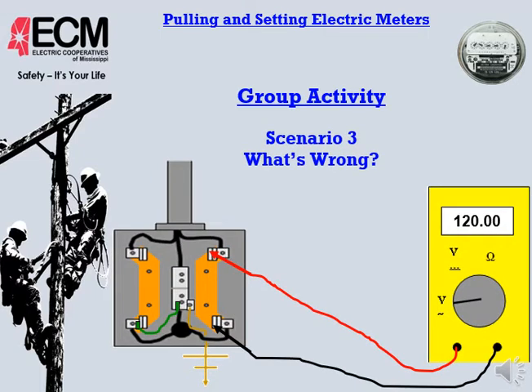Okay, in scenario 3, we get to this point and we're checking voltage and we get 120 volts. Again, we should not get any voltage here. It should be 0 or close to that. We definitely shouldn't get 120 volts on our meter. If we find things here, again, we hit our brakes, we don't set the meter. We've got a backfeed situation. We've got stray voltage coming from somewhere.